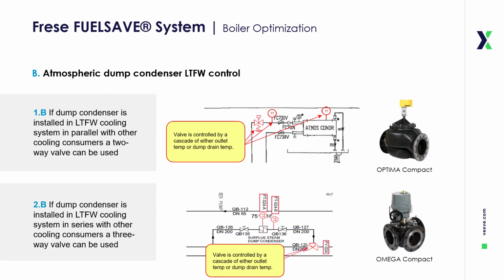The atmospheric dump condenser is a critical component in boiler optimization, utilizing the low-temperature cooling water for condensing steam to be used in the HT circuit and oil-fired boiler. If the dump condenser is installed in parallel with other cooling water consumers, a two-way control valve is sufficient. This valve regulates flow through the condenser while allowing bypass flow directly to the other consumers.